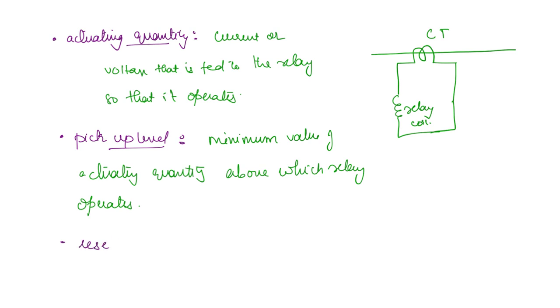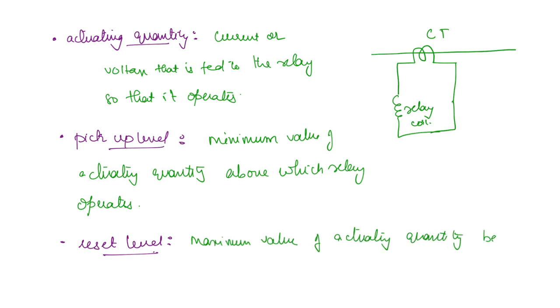Next is the reset level. That means the relay will go back to its original state once the actuating quantity goes below a certain level. The pickup level and reset level may not be the same. So the reset level is the maximum value of actuating quantity below which the relay comes back to its original state. These are some important terms.